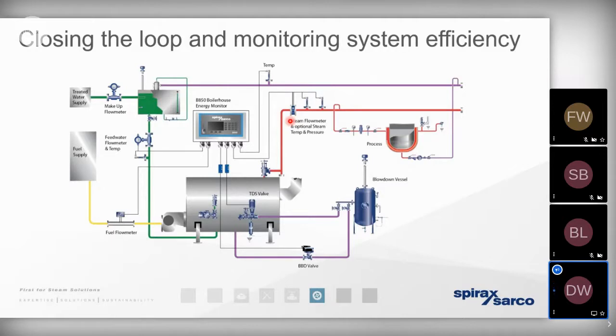Let's say over a period of months, the amount of steam that's being produced and the amount of water that's being supplied from the feed tank to the boiler could have remained relatively stable. But we could have been calling for more and more raw water and more fuel. By taking a reading of the boiler house energy monitor, we can understand the reasons why. For example, if we're not recovering anywhere near as much condensate as we were previously, if we've got a steam trap that's failed in the open position, or if we're venting a lot of flash steam away, well, we need to replace that with more raw water. And we then need to bring that water up to the point where we can generate steam again. So it gives us a good understanding not only of where that inefficiency exists, but it tells us the burden of that inefficiency in financial terms.